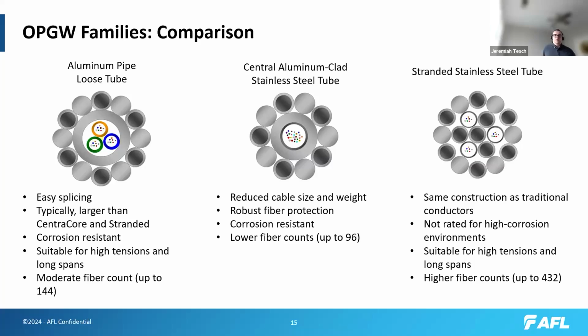Now, typically for OPGW, we also use two types of wires. So you have aluminum alloy, which is the solid gray there, and then aluminum clad steel with the dark core. So that is essentially coated with aluminum powder to provide corrosion protection as well as some level of conductivity on the surface. And so just to provide that background on the wires there, continuing now with the CentraCore or the central stainless steel tube style.